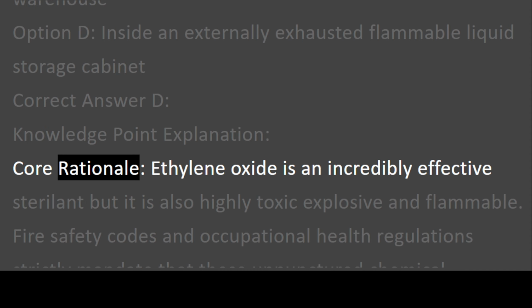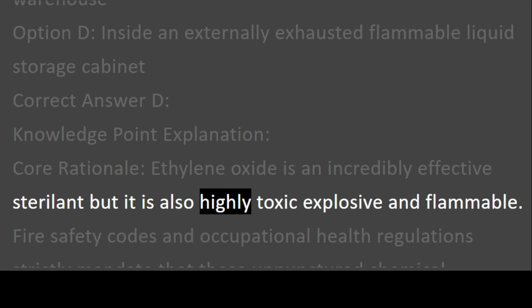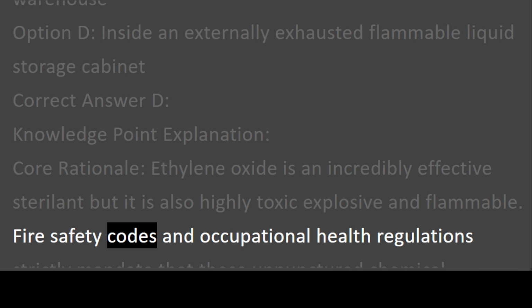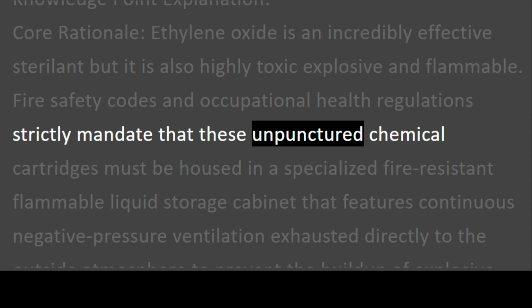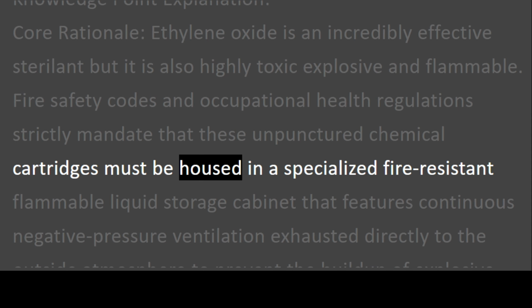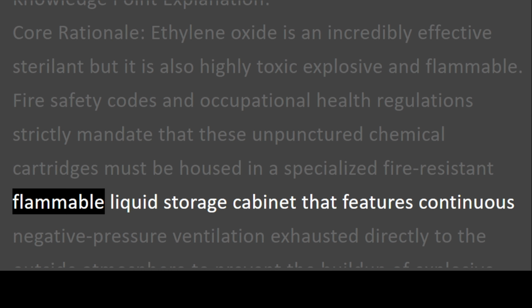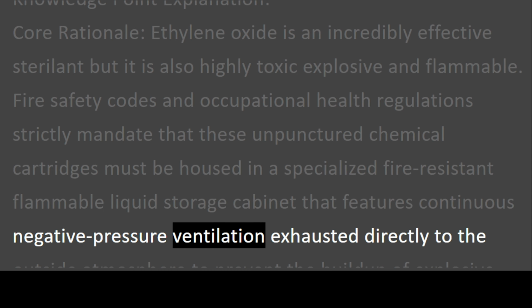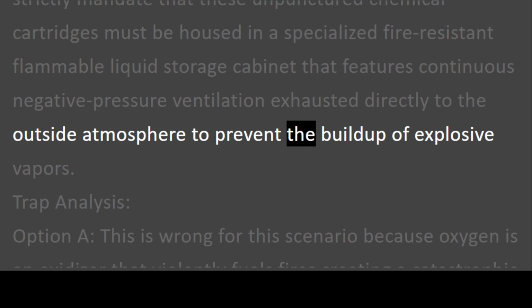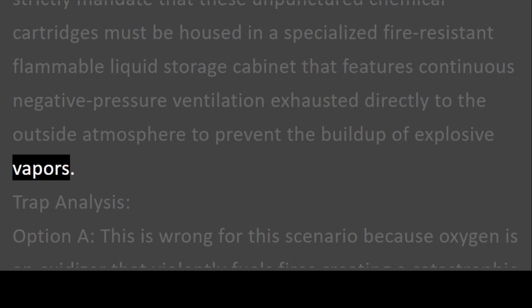Core rationale. Ethylene oxide is an incredibly effective sterilant, but it is also highly toxic, explosive, and flammable. Fire safety codes and occupational health regulations strictly mandate that these unpunctured chemical cartridges must be housed in a specialized fire-resistant flammable liquid storage cabinet that features continuous negative pressure ventilation, exhausted directly to the outside atmosphere to prevent the buildup of explosive vapors. Trap analysis.